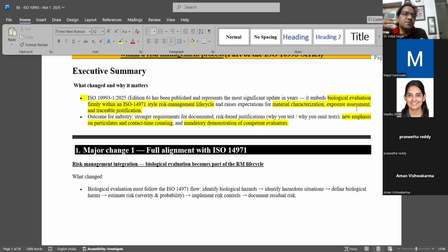based on 2025, you need to relook at your exposure time based on the reuse of your device. If you are reusing the device, it could be off label or on label. If the device is reused, the exposure time will amplify. Suppose you used it for 6 hours in one patient, and you have used the same device in another 5 patients. It is between 0 and 24 hours where it is in limited contact. Now it enters into prolonged contact because you have reused it, and there will be multiple additions to that, or you need to multiply by the number of hours you use. So a lot of devices from limited will enter into prolonged.